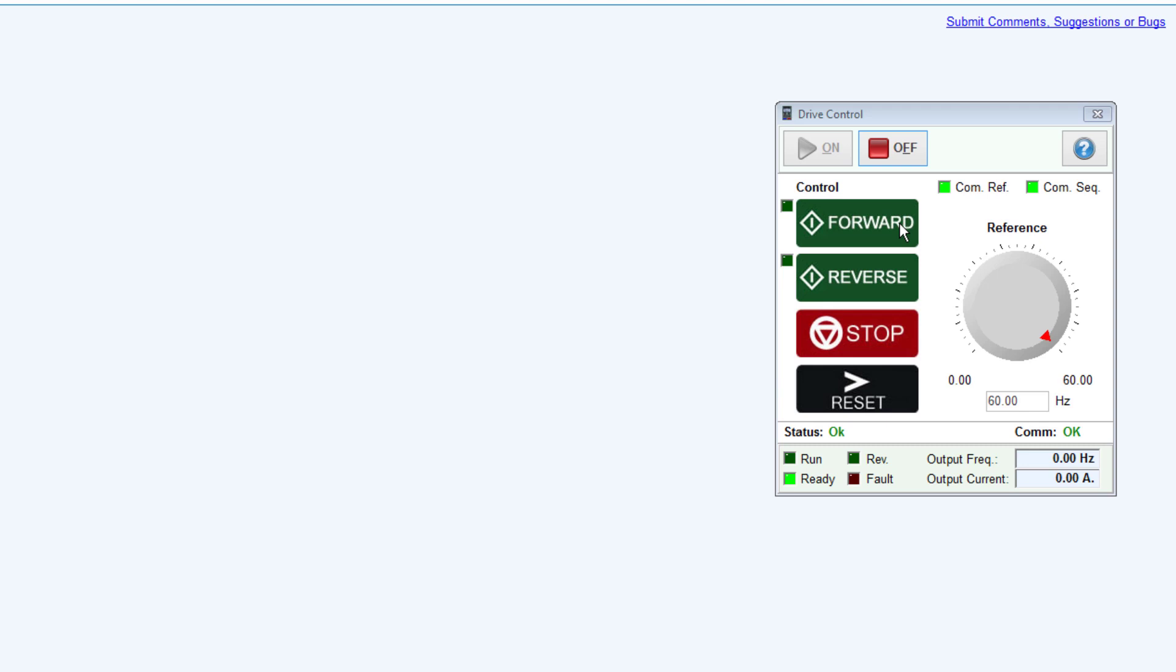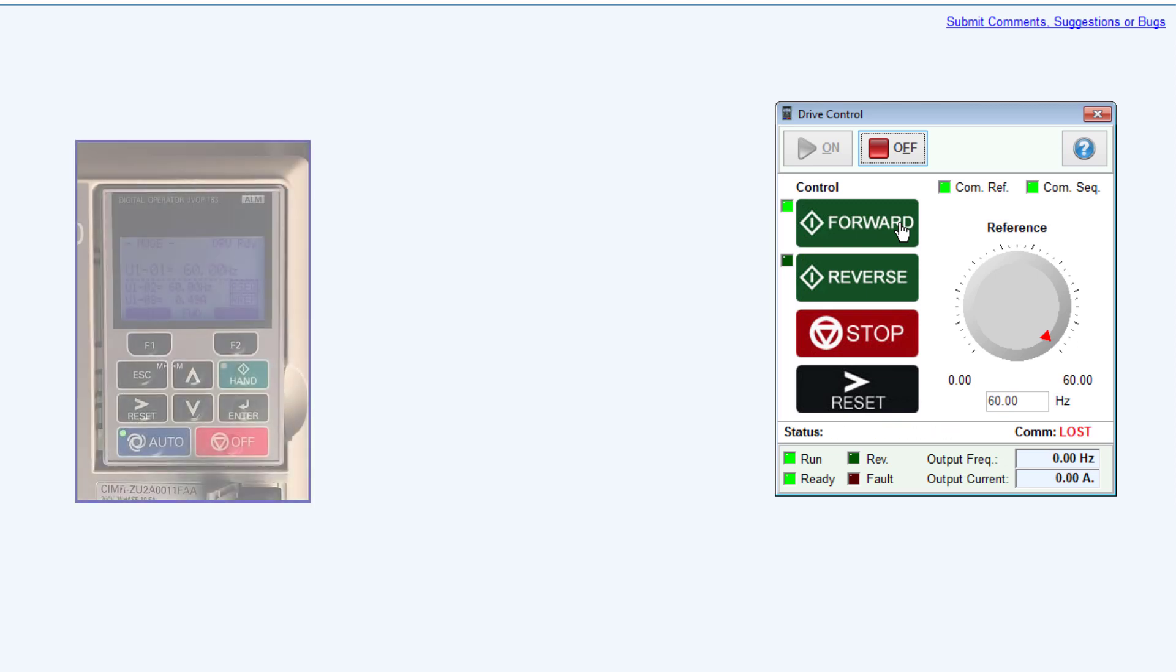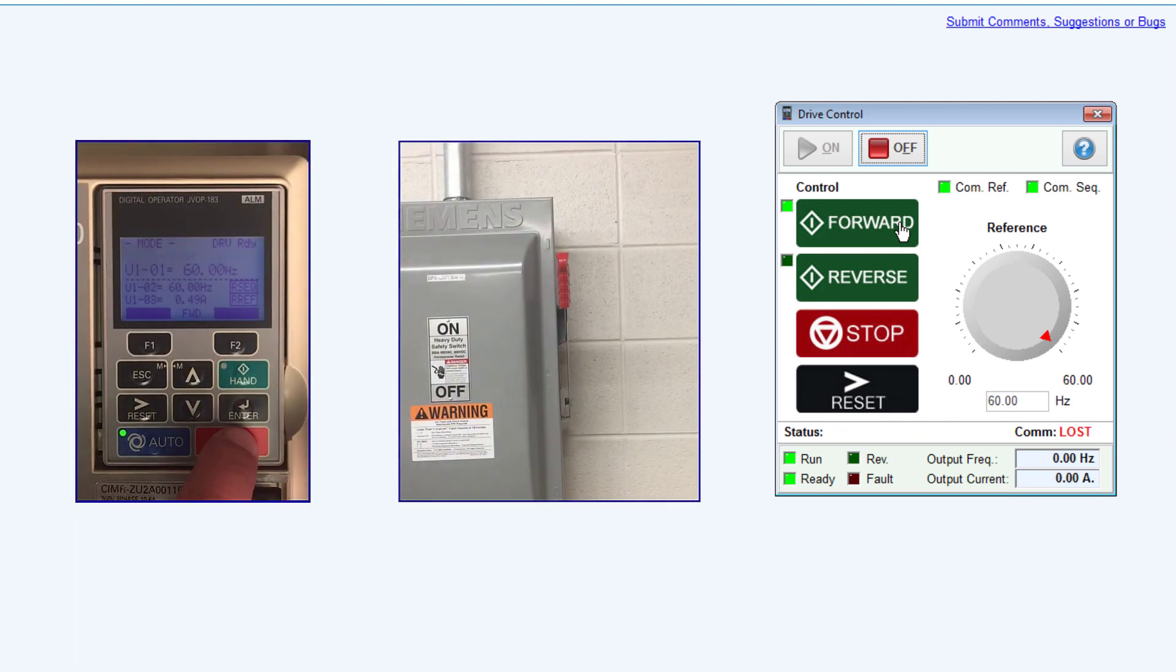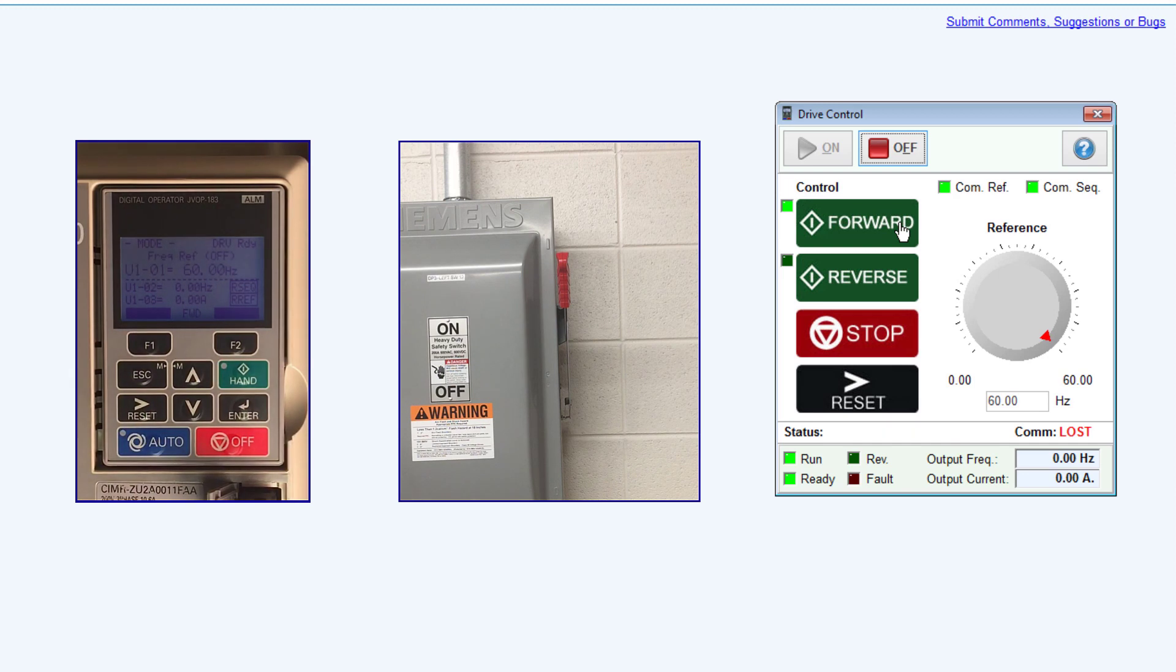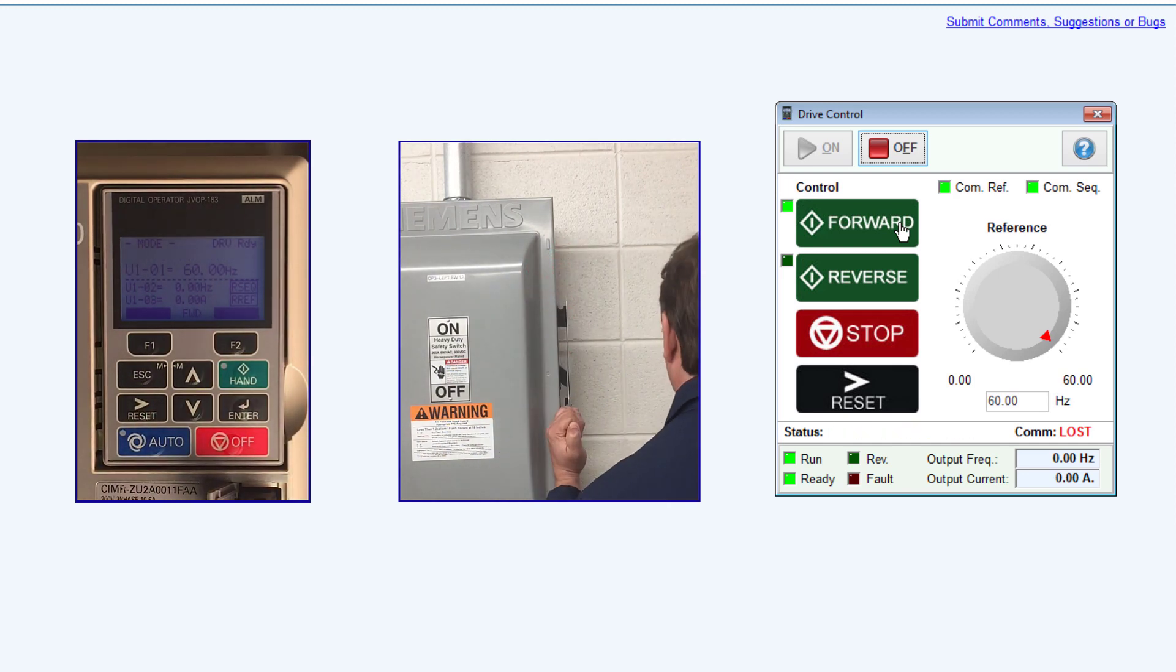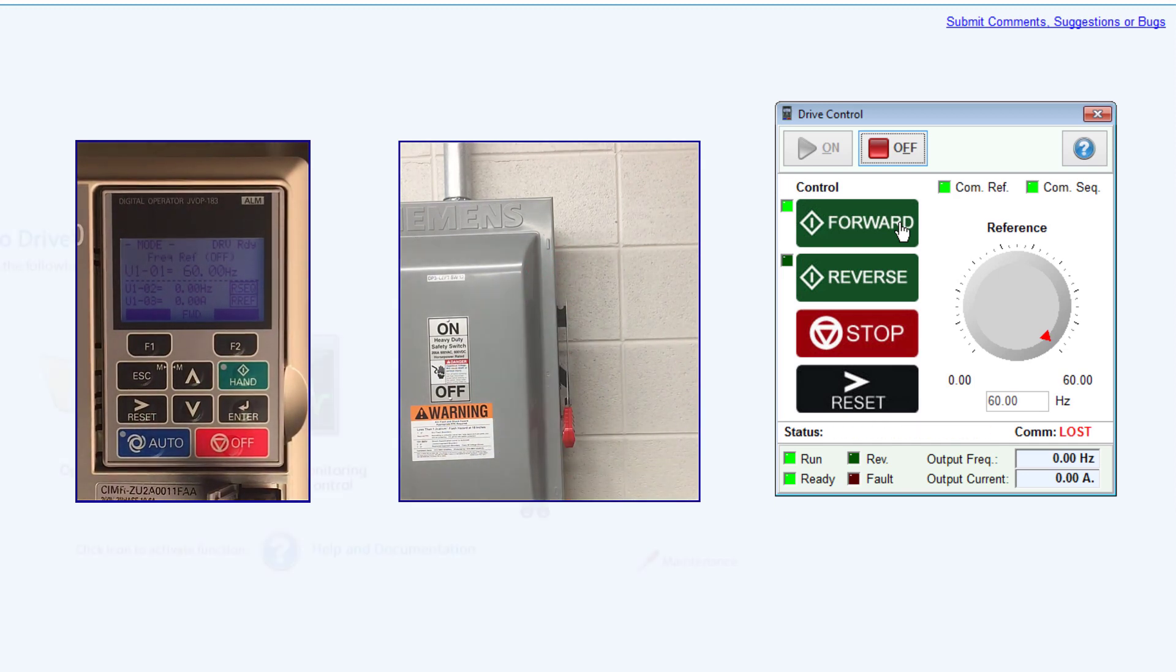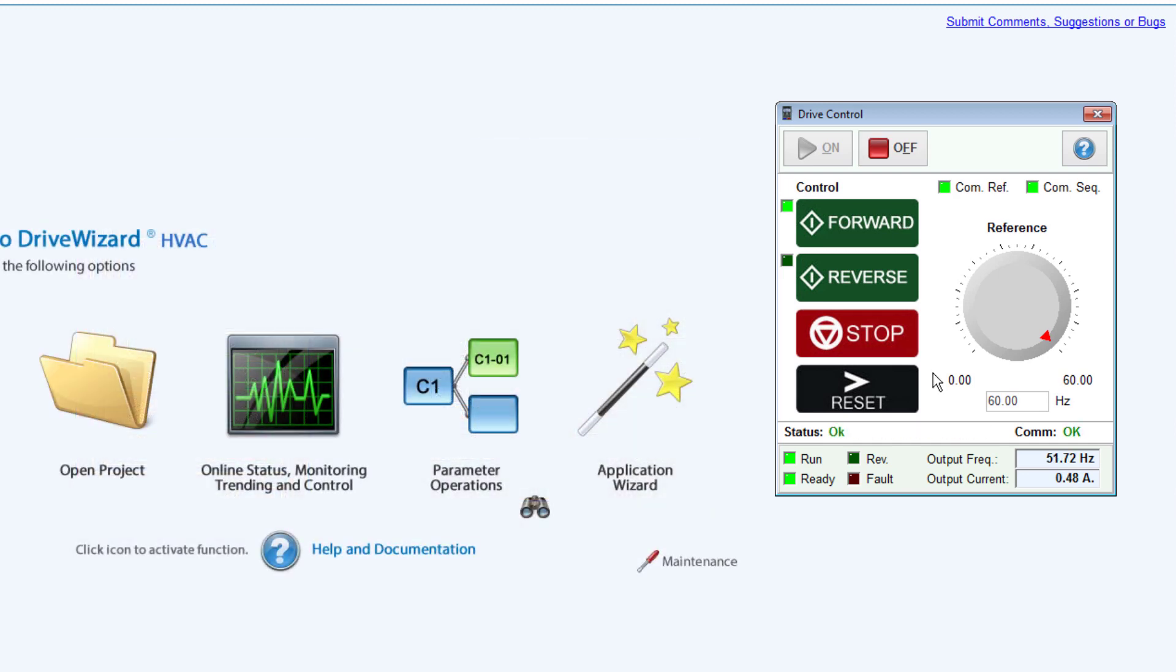If communication is ever lost from, say, a loose or disconnected cable, the program will flash 'Communication Lost' and 'Communication Offline' for the status. Cease drive control operation by pressing Off on the drive's keypad or by powering down the drive.